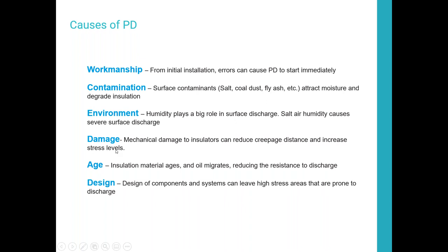Damage: mechanical damage to the insulators. Again, nicks, cuts, impacts that could cause damage. If we're talking about a solid porcelain insulator, high wind conditions can cause cracks and damage to the insulator. Even micro cracks within the ceramics can be the location point of partial discharge that will slowly break down that insulation over time.